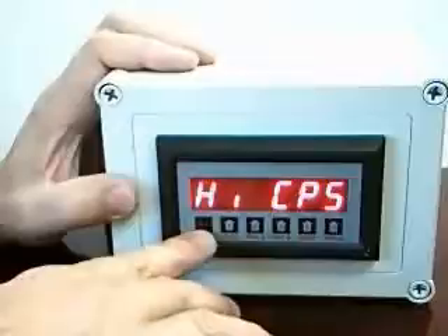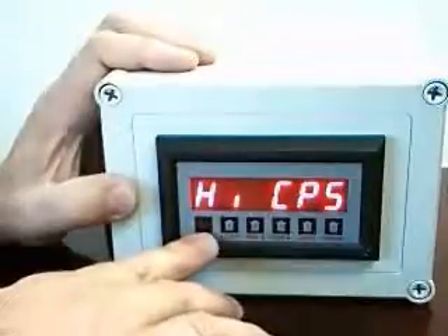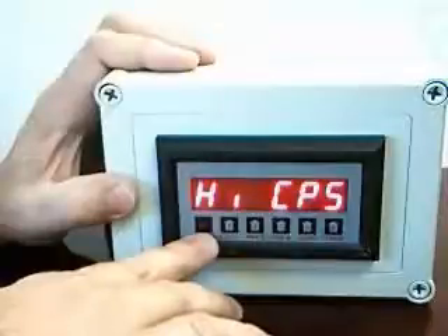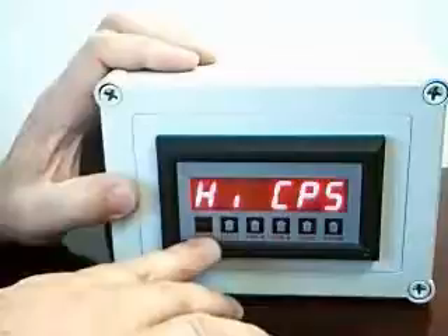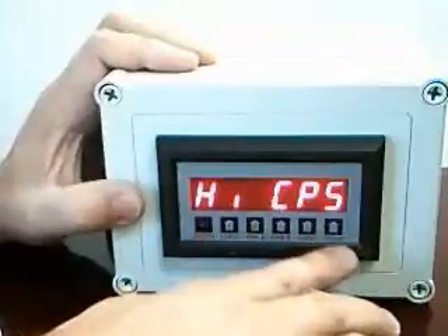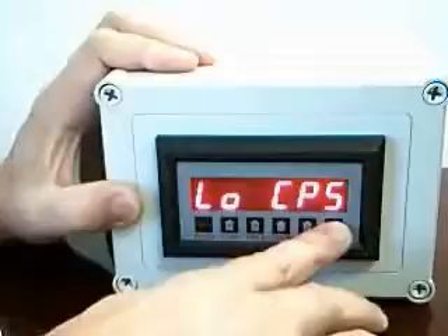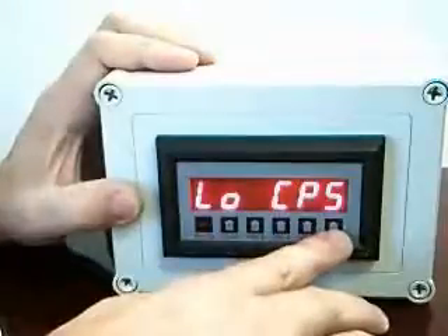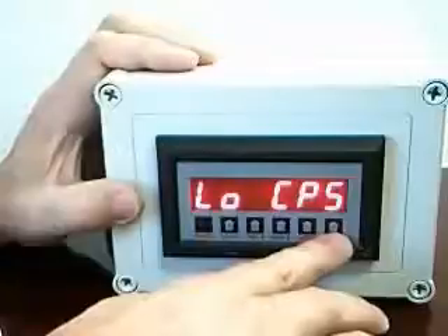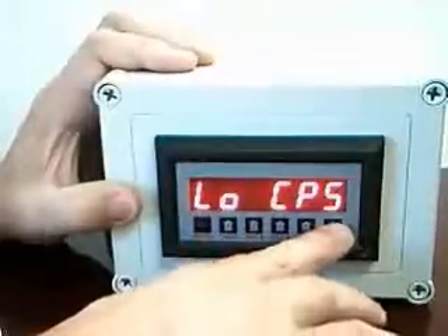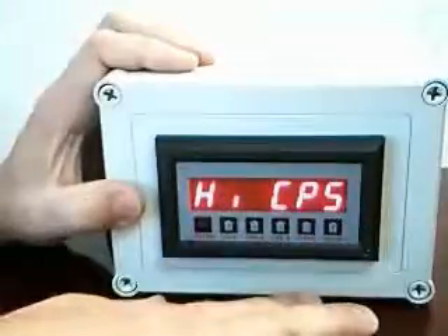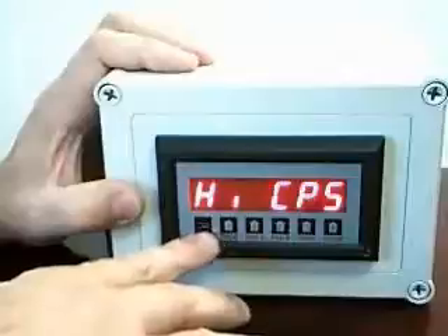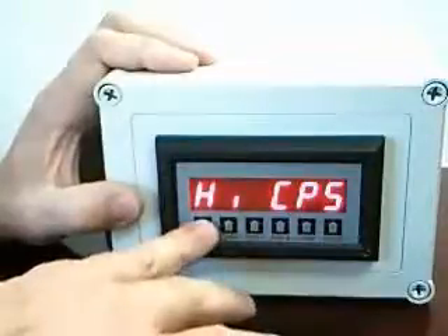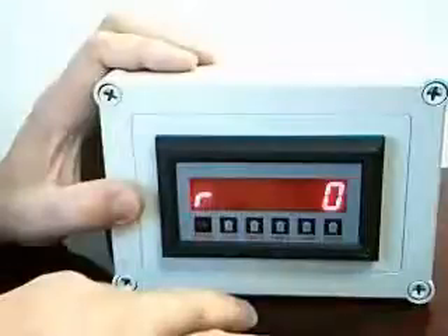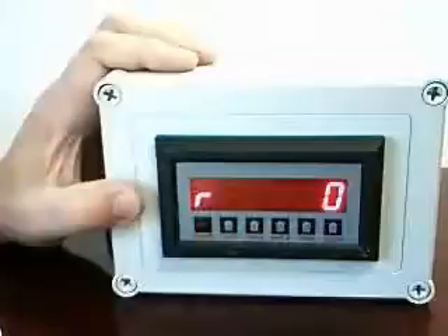The final menu in this group informs the unit whether this is going to be a high-speed pulse or a contact closure input. In this case, high counts per second is indicating the unit is going to be used with an electronic pulse output. The alternative selection, which can be obtained or viewed by pushing the program button, is low CPS, or low count speed. This is what would typically be used with a contact closure input. We're going to assume that the instrument is going to be receiving a voltage pulse and needs the high count speed. To finalize that selection, I hit Enter. At this point, the unit returns to the run mode and displays the flow rate for me.